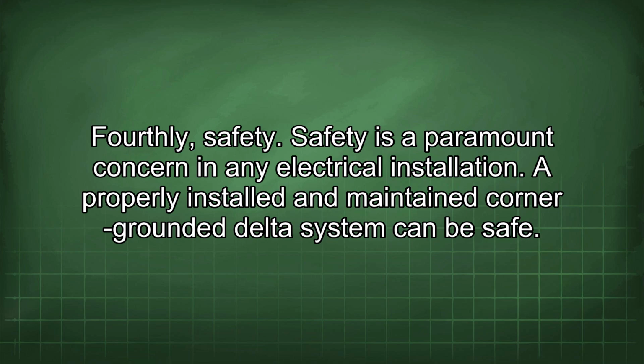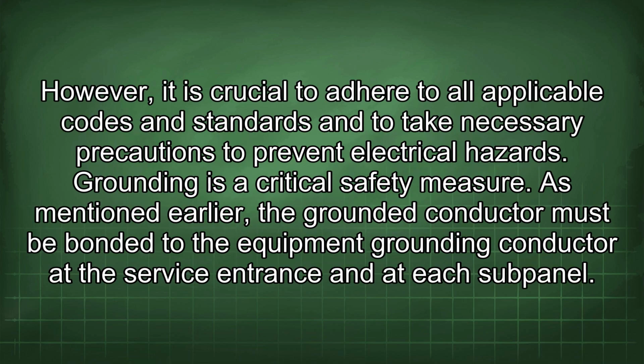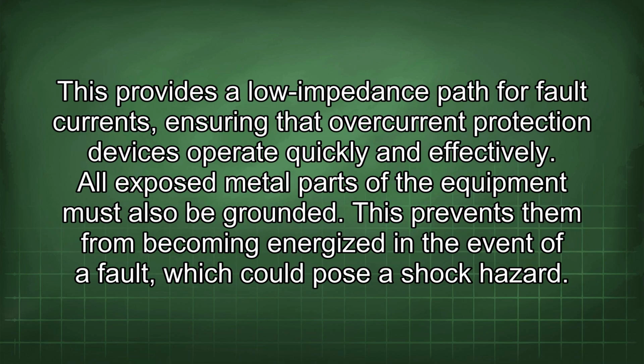Fourthly, safety. Safety is a paramount concern in any electrical installation. A properly installed and maintained corner-grounded delta system can be safe. However, it is crucial to adhere to all applicable codes and standards and to take necessary precautions to prevent electrical hazards. Grounding is a critical safety measure. As mentioned earlier, the grounded conductor must be bonded to the equipment grounding conductor at the service entrance and at each subpanel. This provides a low impedance path for fault currents, ensuring that overcurrent protection devices operate quickly and effectively. All exposed metal parts of the equipment must also be grounded. This prevents them from becoming energized in the event of a fault, which could pose a shock hazard.